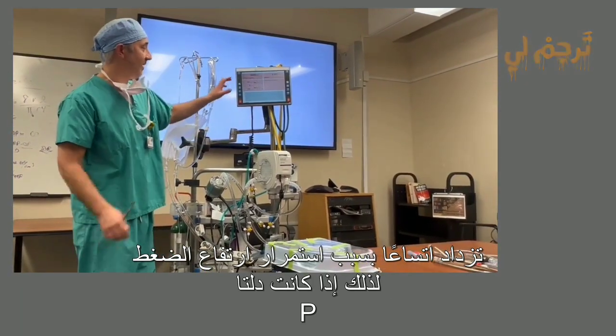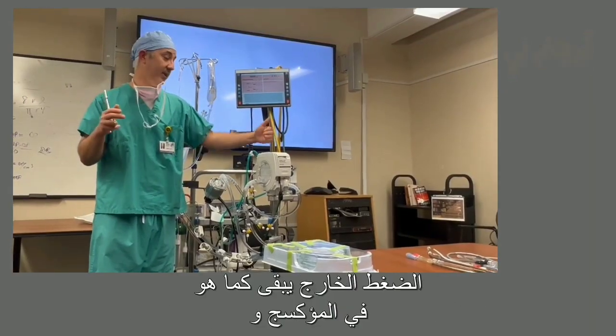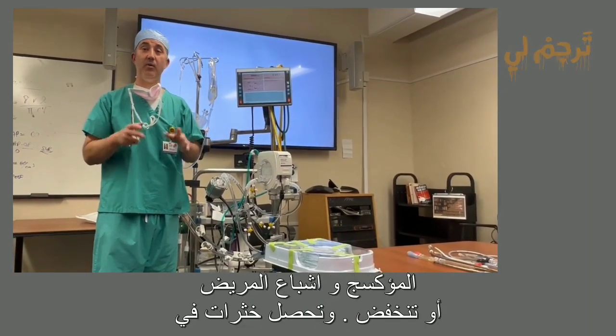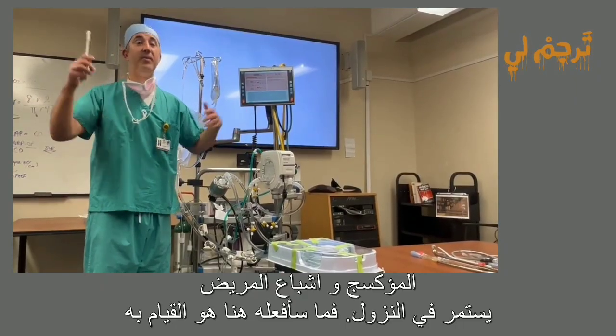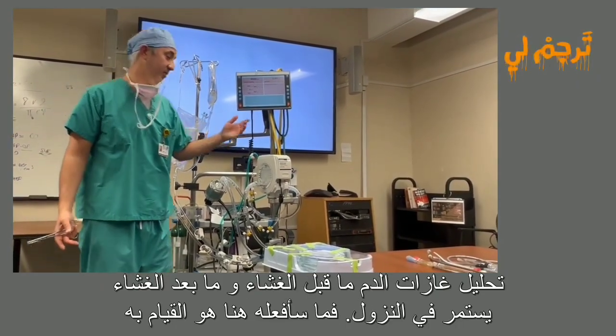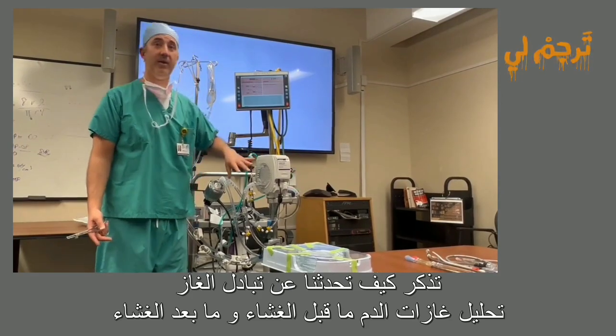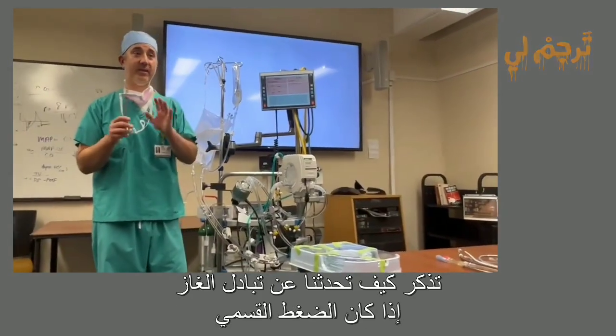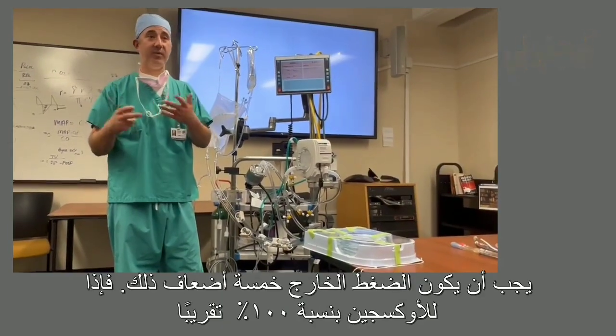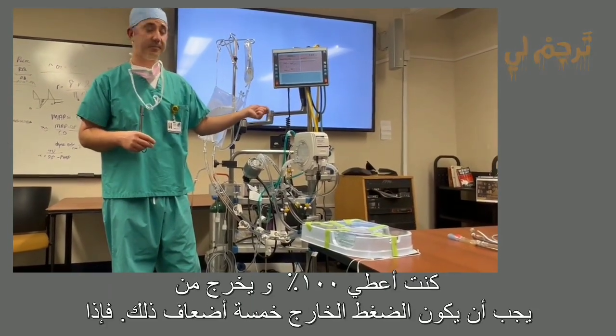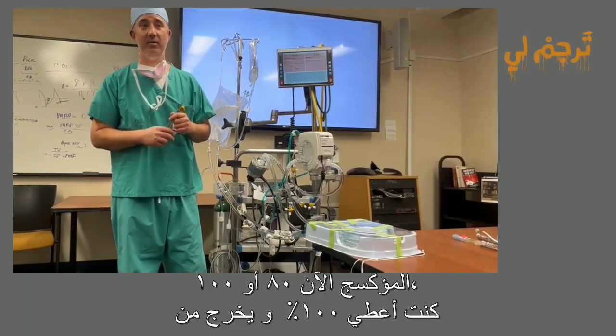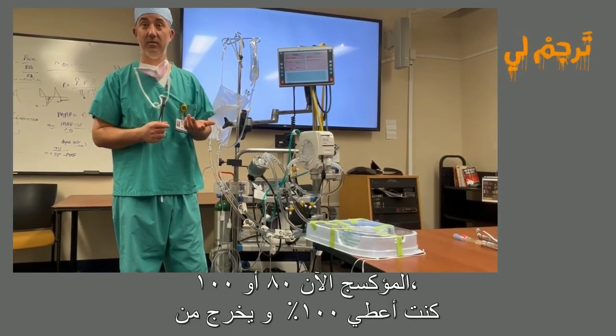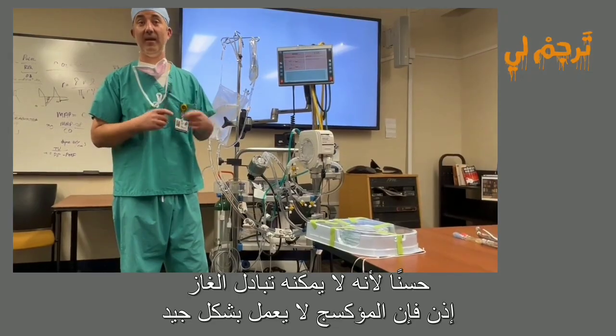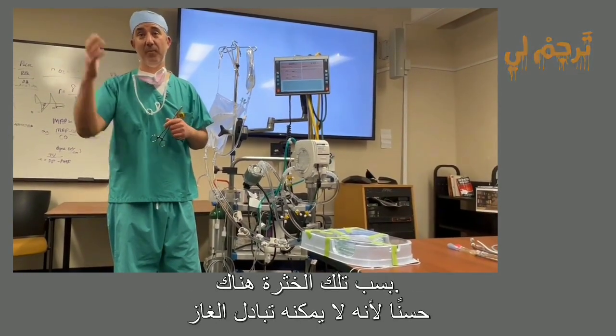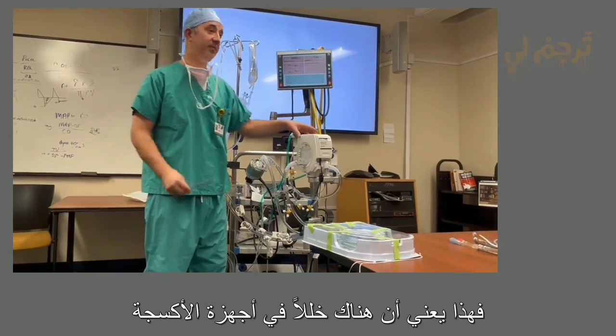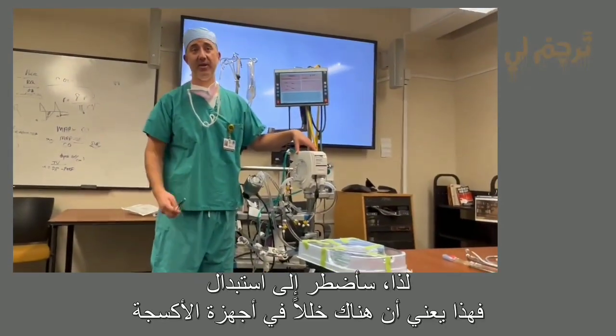So if my delta P is getting wider because the pressure going into the oxygenator is going up and the pressure coming out is staying the same or going lower, you have clots in the oxygenator and the patient's sats are going down. What I would do then is do a pre-membrane ABG and a post-membrane ABG. Remember how we talked about that gas exchange. If I'm at 100%, the PO2 roughly coming out should be 5 times that. If I'm at 100% and the PO2 coming out of the oxygenator is now 80 or 100, then the oxygenator is not working very well because it can't exchange that gas because of all that clot in there. And if the patient is desatting, then this poorly functioning oxygenator is the cause of it. So then I would have to change out the oxygenator.